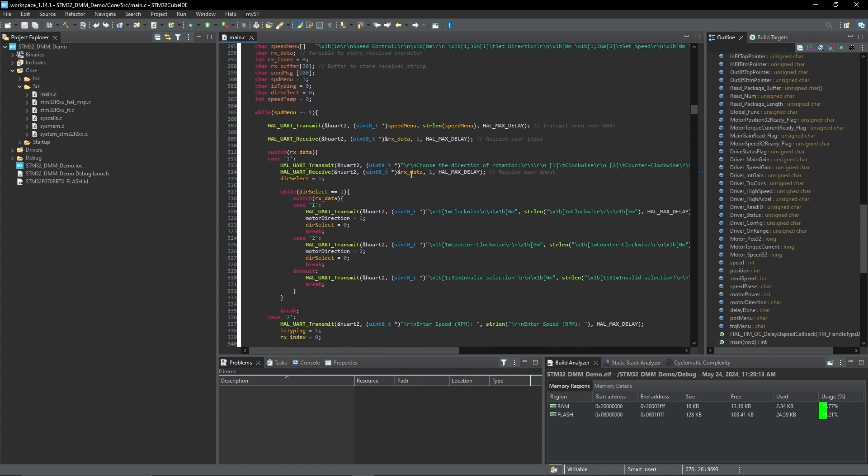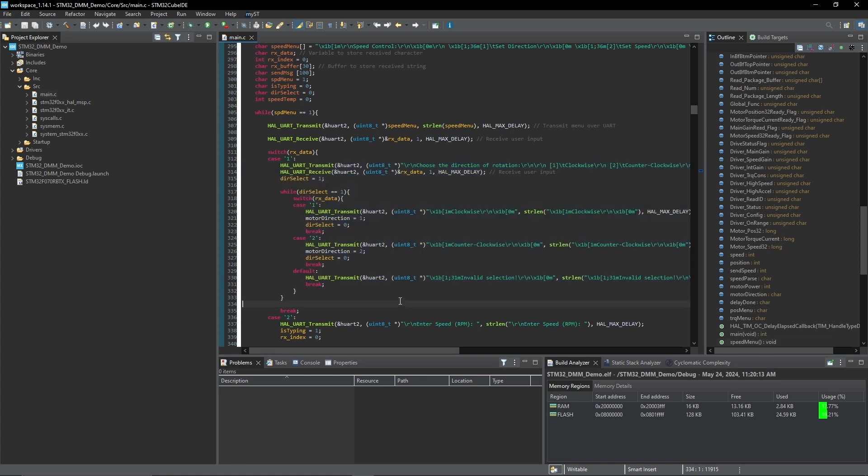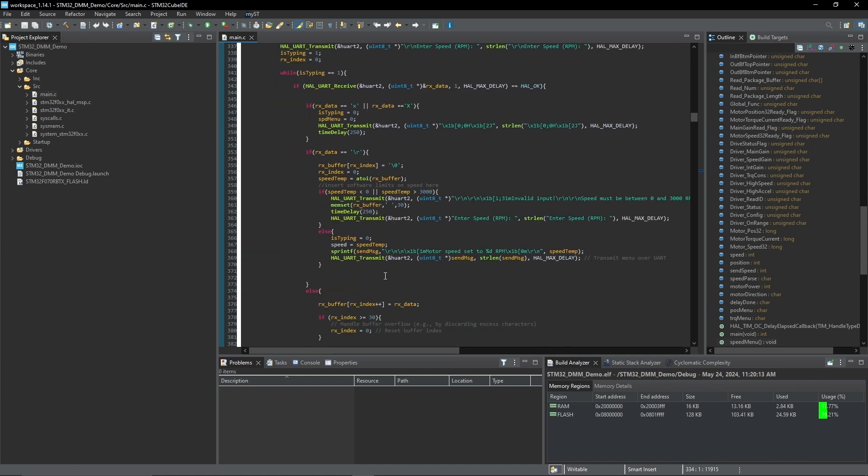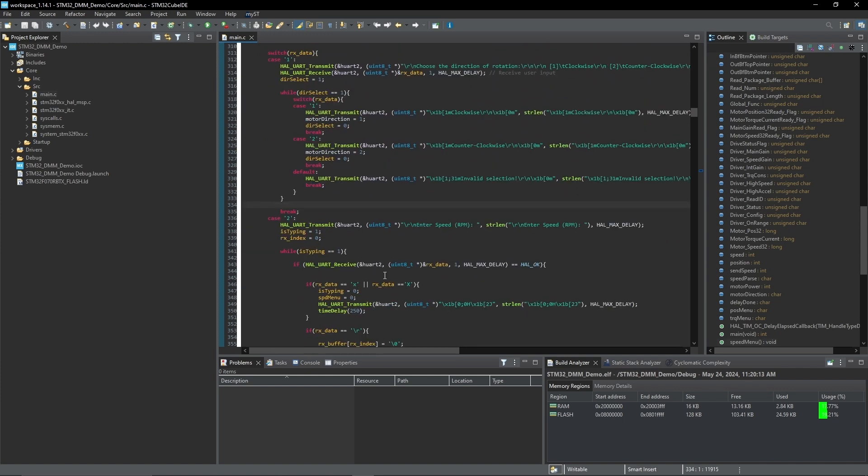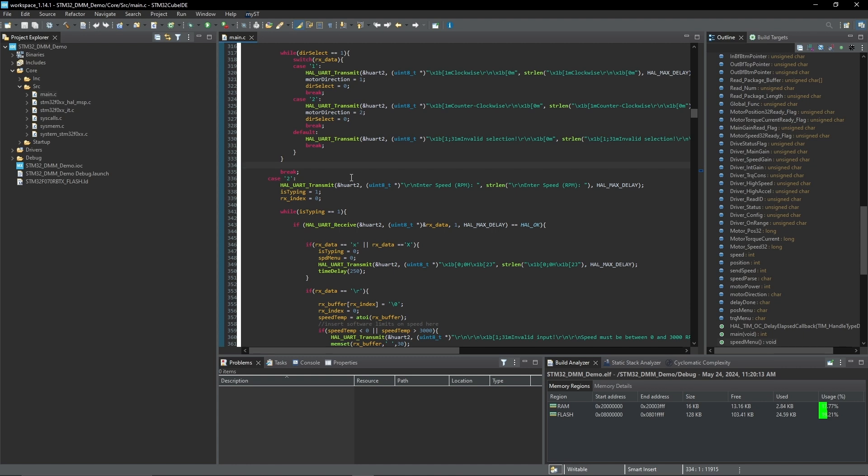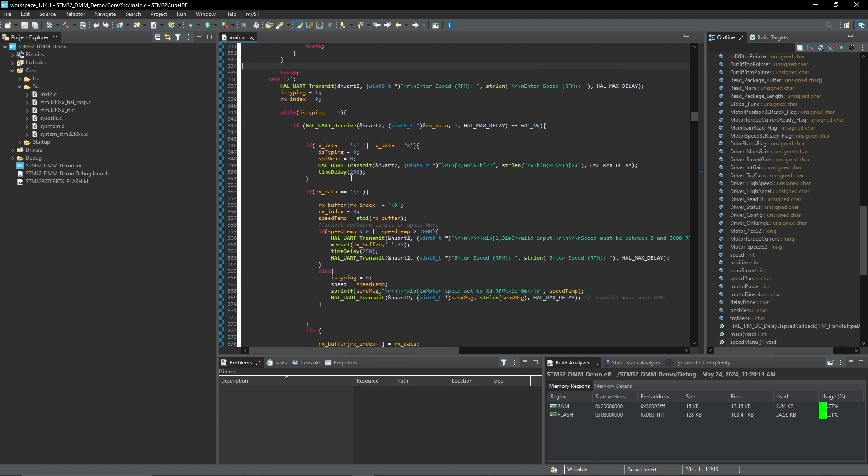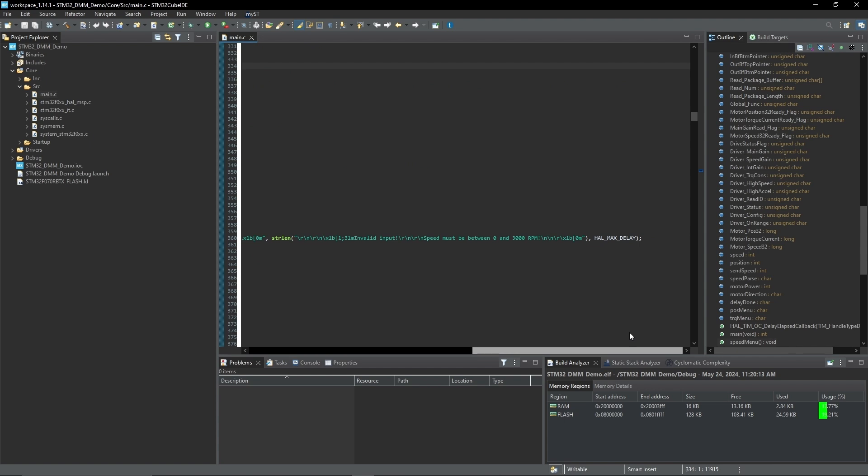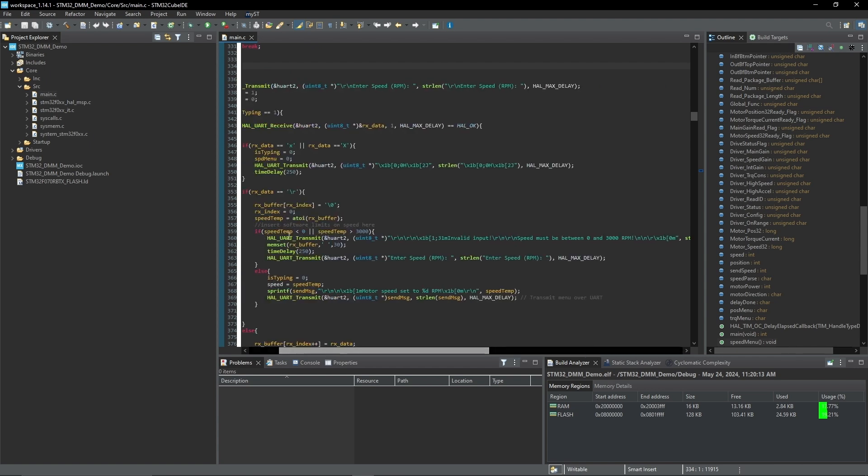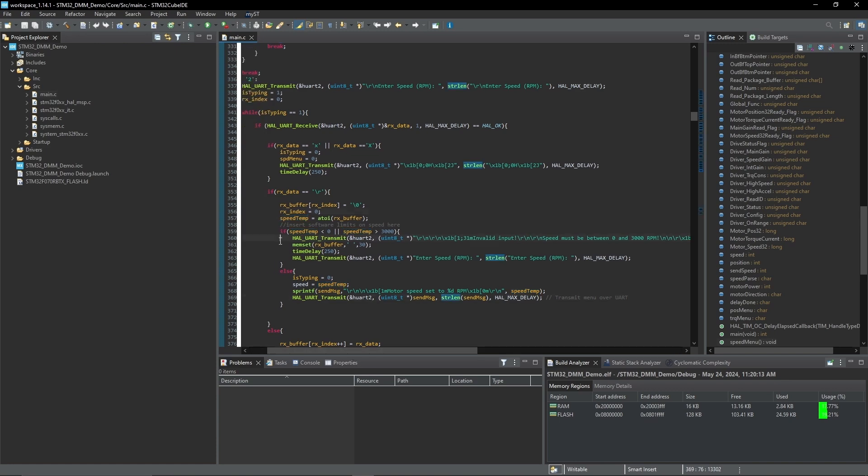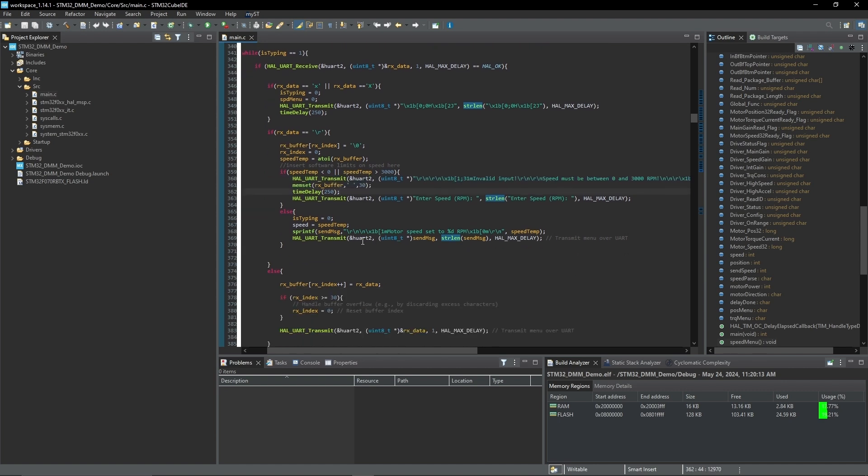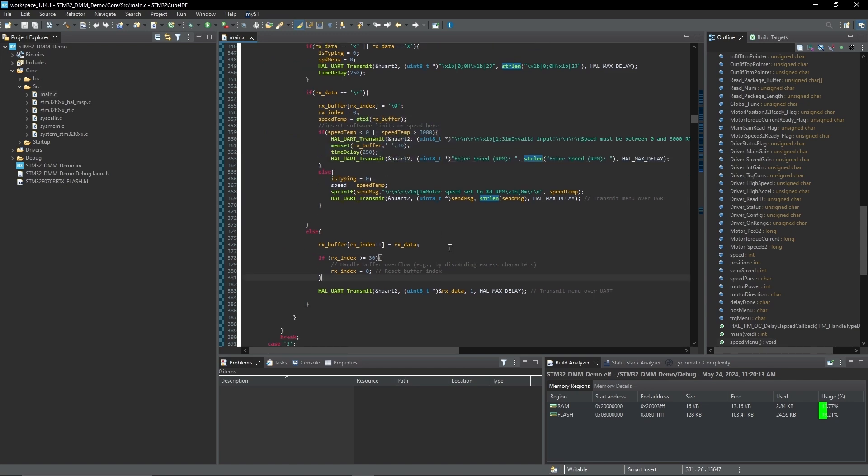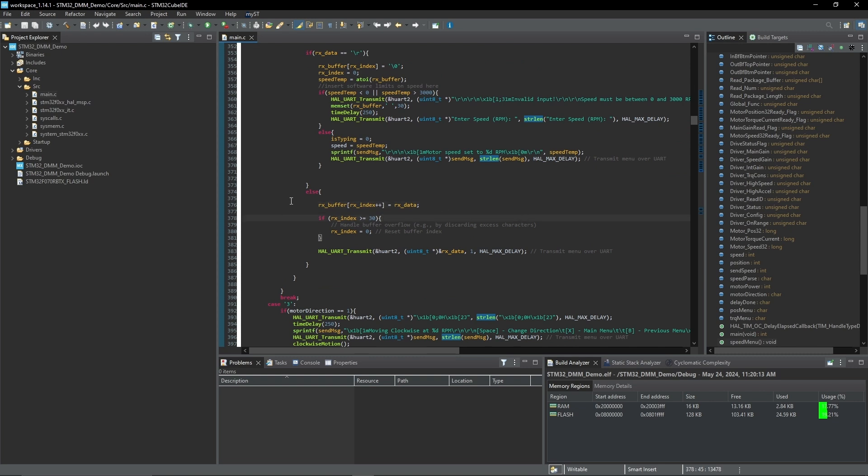The speed menu, as I said before, looks a lot like the main menu with the different selections. There are some limiting factors involved here. If a speed gets set too high, above 3000 RPM, I believe our motors are good to 5000 RPM maximum, but I used 3000 just as that's the rated speed. Didn't want to push the motor too hard just for the purpose of demo. It will return an error and not allow you to set the speed higher. That's a little tiny safety feature that's just software based, very easy.